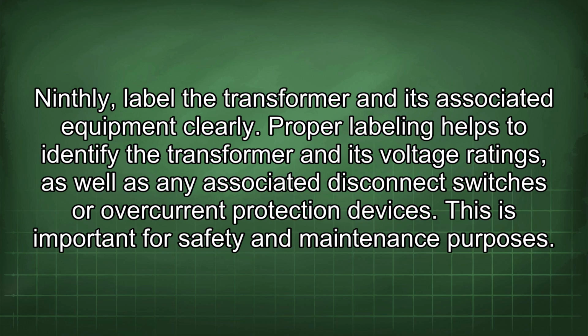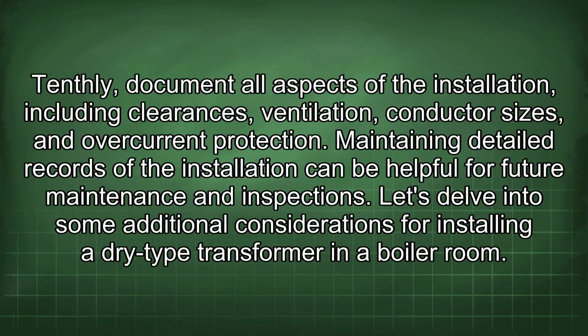Ninthly, label the transformer and its associated equipment clearly. Proper labeling helps to identify the transformer and its voltage ratings, as well as any associated disconnect switches or overcurrent protection devices. This is important for safety and maintenance purposes. Tenthly, document all aspects of the installation, including clearances, ventilation, conductor sizes, and overcurrent protection. Maintaining detailed records of the installation can be helpful for future maintenance and inspections.